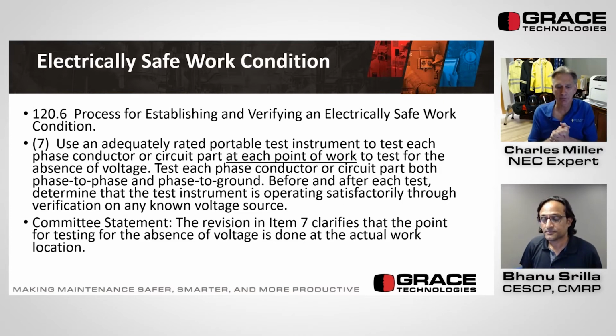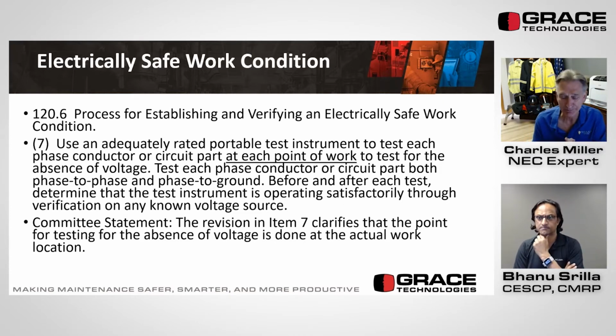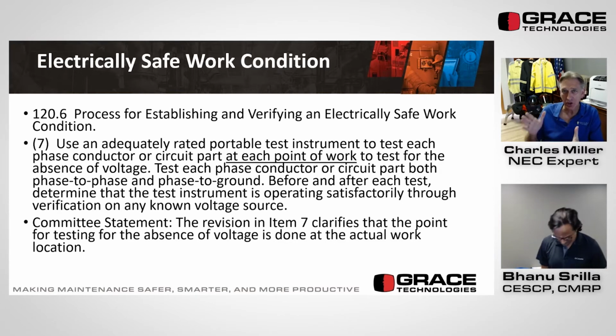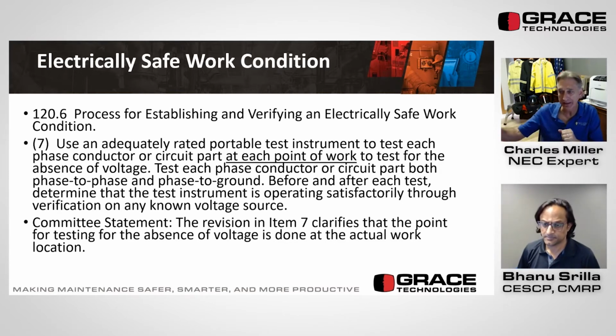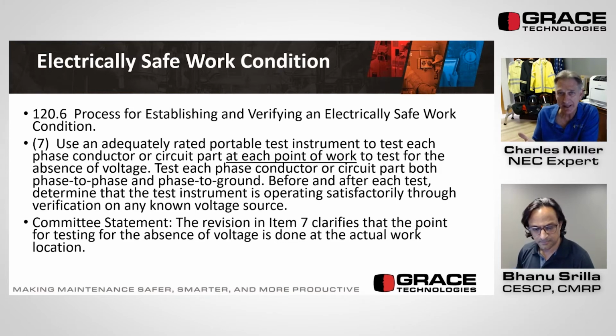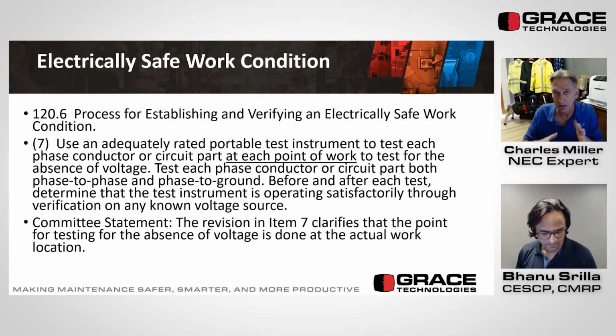All right, let me give you another example. You need to change a motor out, and there is a disconnect switch within 4 feet of the motor. You've got Sealtite or flex Greenfield going down to the motor, and you know that power is coming from that disconnect to that motor. Well, you turn the disconnect switch off, lock it out, tag it out, and you test for the absence of voltage on the load side of that disconnect. Again, testing your meter, testing phase to phase, phase to ground, and testing your meter again. Then you close the door, and at that point, the way it is now, we can take our shock and arc rated PPE off and get into that motor.